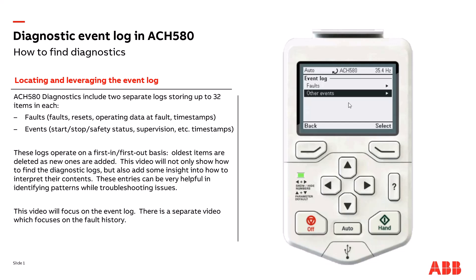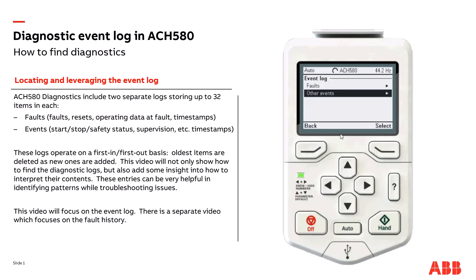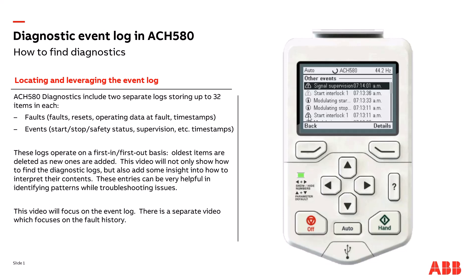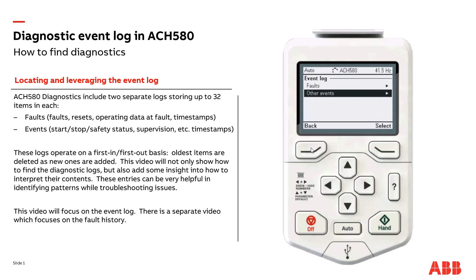I'll make the safety again and start again — you can see that sequence of events. I also have a supervision program in the drive, so let me raise the setpoint. The supervision is set for 40 Hz, so this triggers supervision. Looking at the event log: Signal Supervision is active, shown in bold. When it's grayed out it means it's inactive. Now I'll reduce the setpoint back below the trigger and we should see that the supervision clears — which it does.